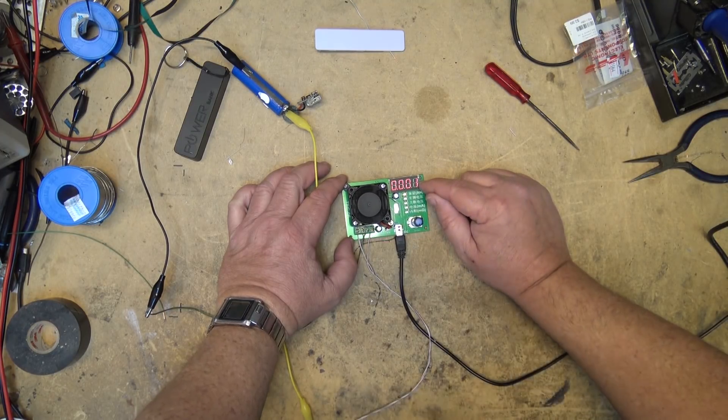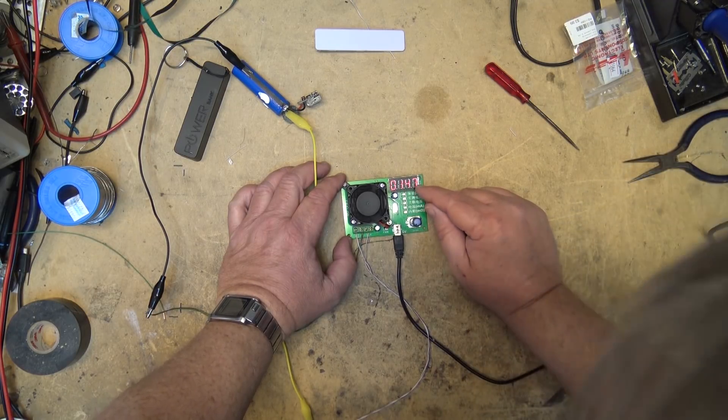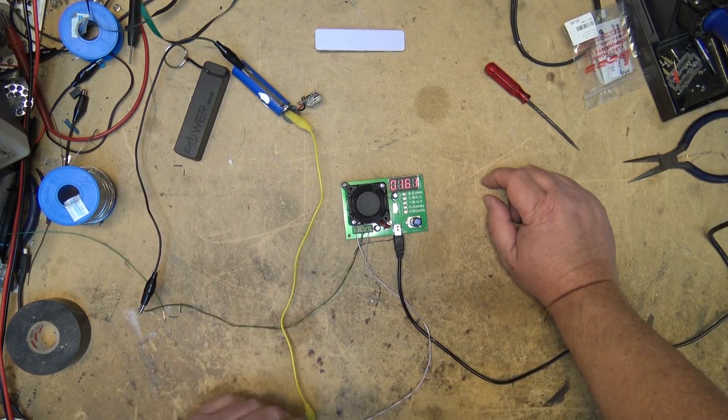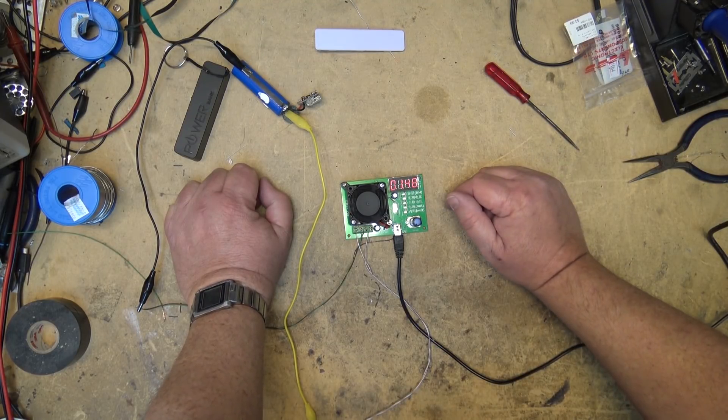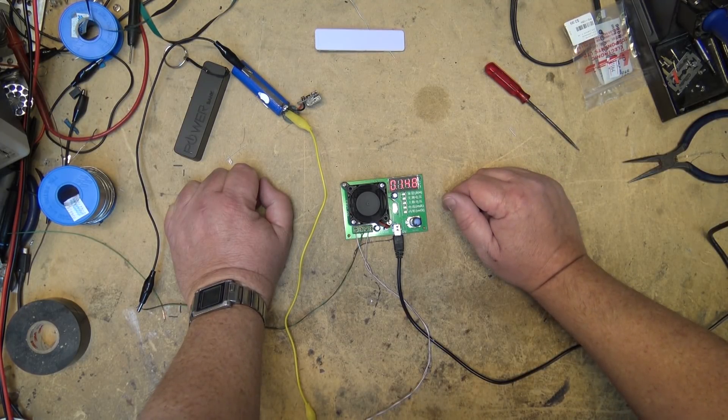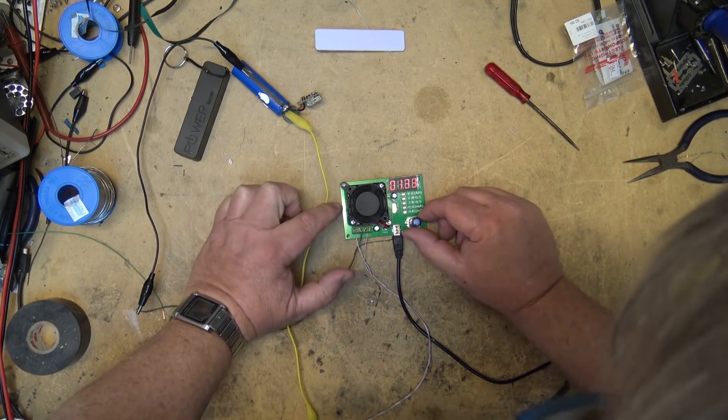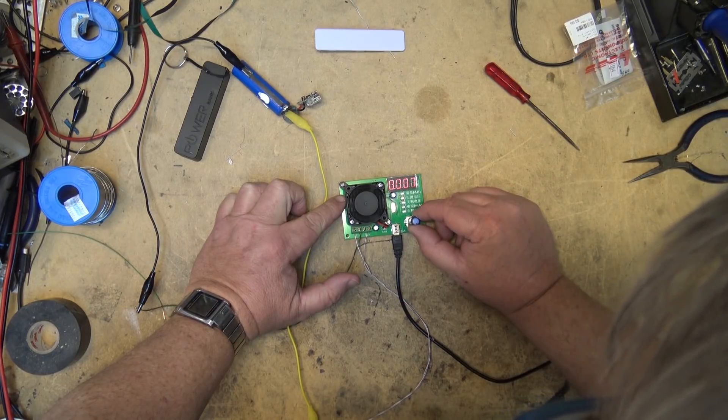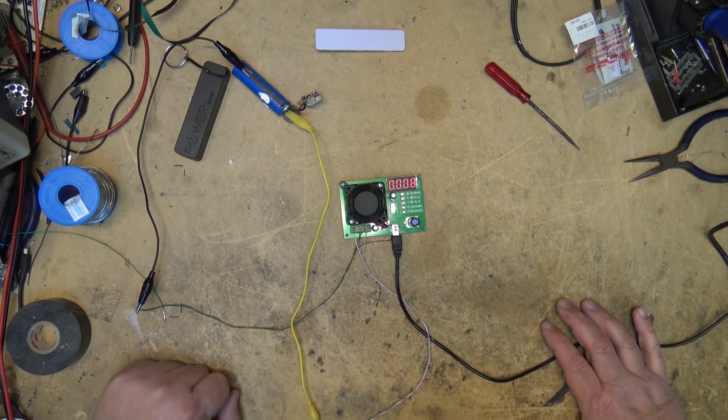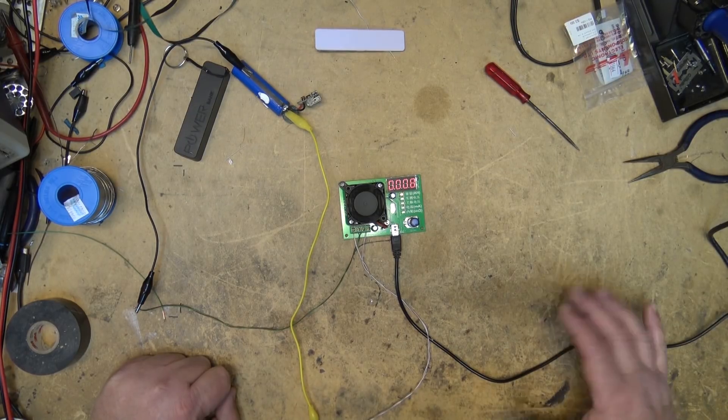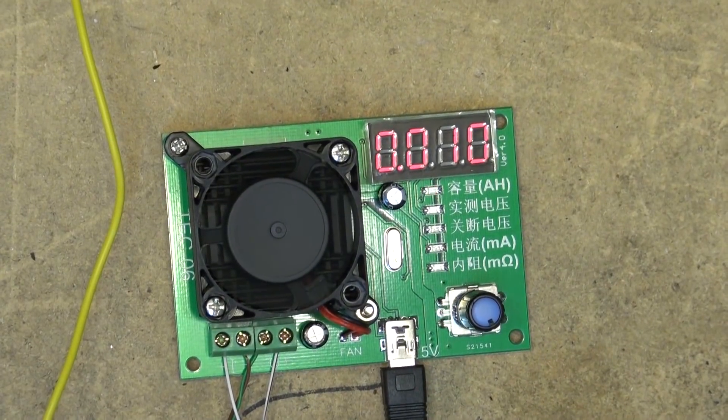This is going to count our amp hours, and here is our internal resistance of the battery. This thing is now going to discharge the battery and as the battery discharges at a one amp discharge rate it will calculate our capacity in amp hours. So if we switch it up to amp hours here, this will count our amp hours for the battery until the battery goes dead. Now we'll just let this thing discharge and we can time how long it takes to discharge the battery.